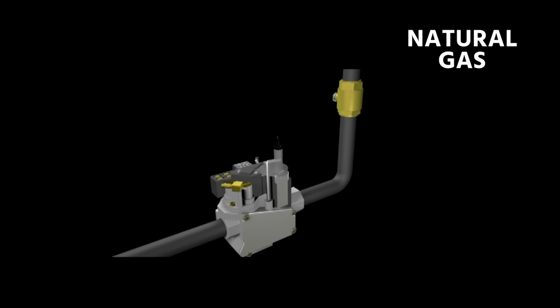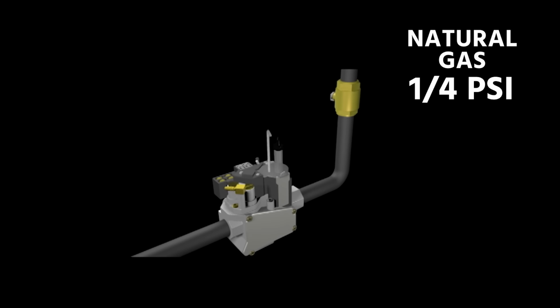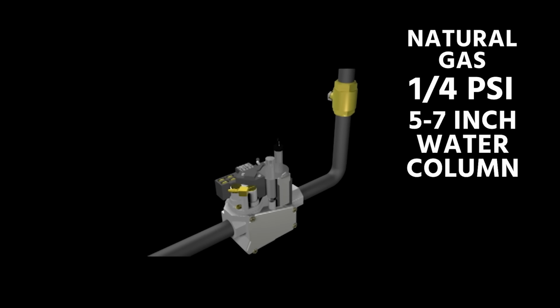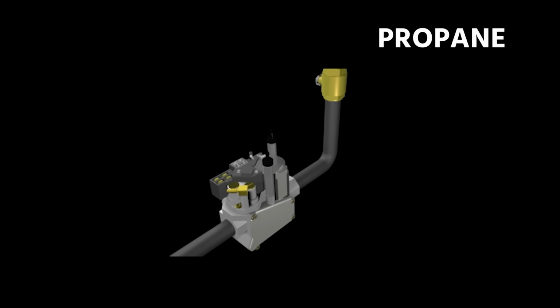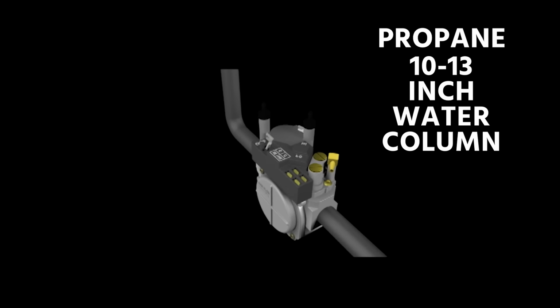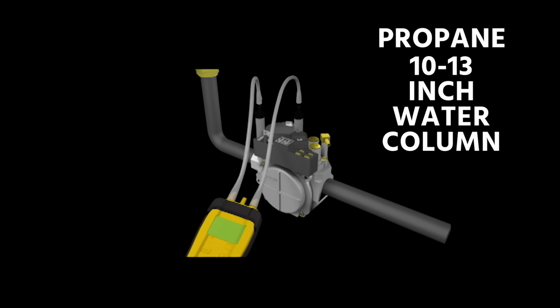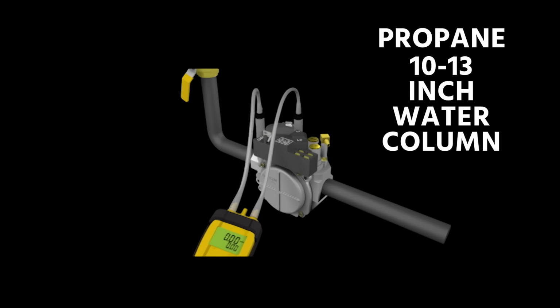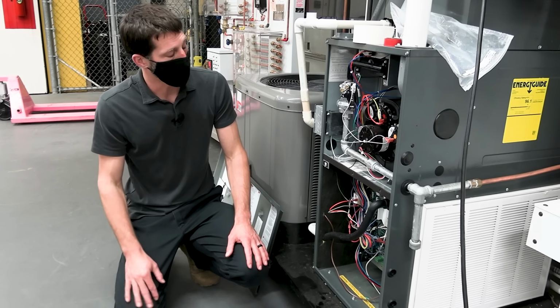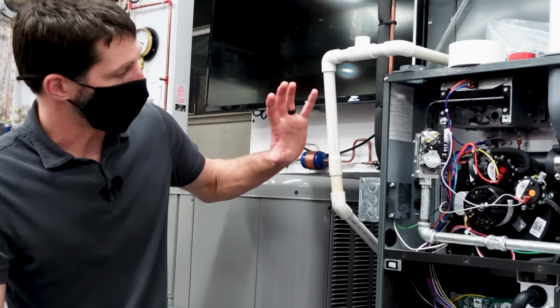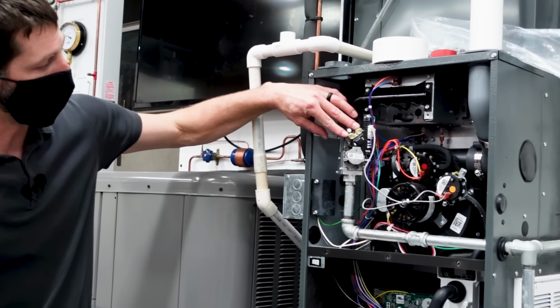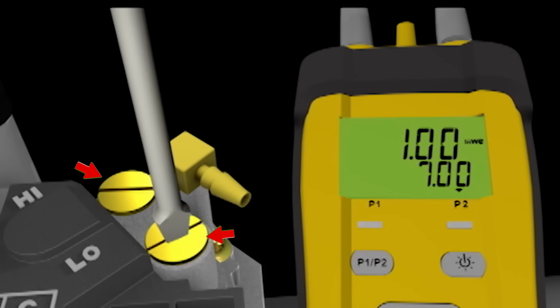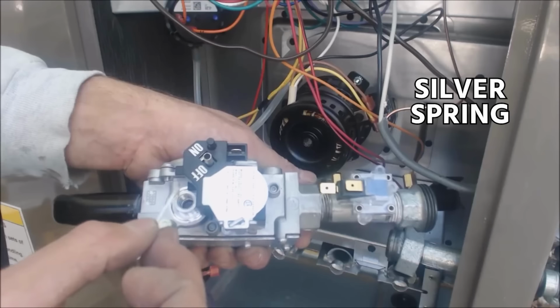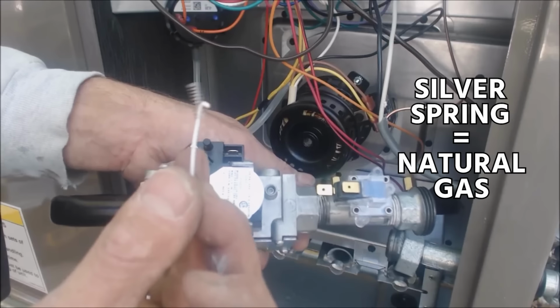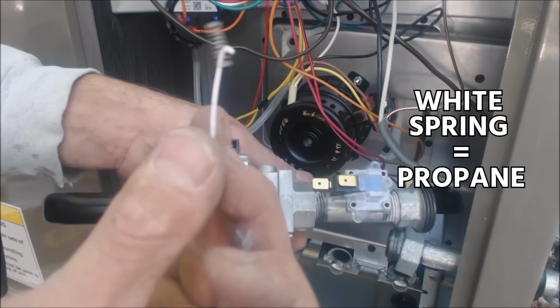So you know, natural gas runs at about 1/4 of a PSI. It's about 5 to 7 inch water column when it comes in, and propane will be around, say, 10 to 13 inch water column, depending on how high the pressure is adjusted on the regulator outside at the propane tank. This one, you can completely identify that this is a 2-speed gas furnace because there's 2 spring sets right here. And so if you ever see the spring inside, the real silvery one, that's for natural gas, and the whiter one, that's usually for propane, which is also referred to as LP.